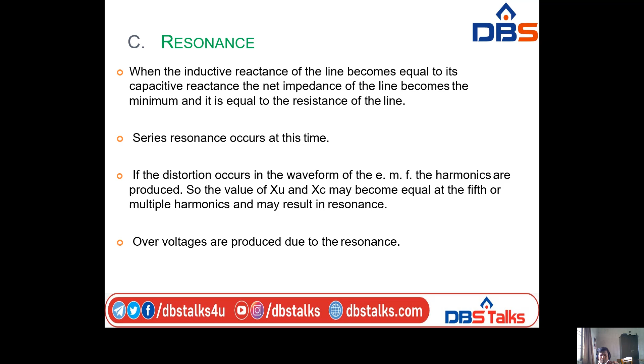If distortion occurs in the waveform of the EMF, harmonics are produced. So the values of XL and XC may become equal at the fifth or multiples of harmonics, which may result in resonance. The overvoltage is produced due to the resonance. That is nothing but transients occurring in the transmission system.